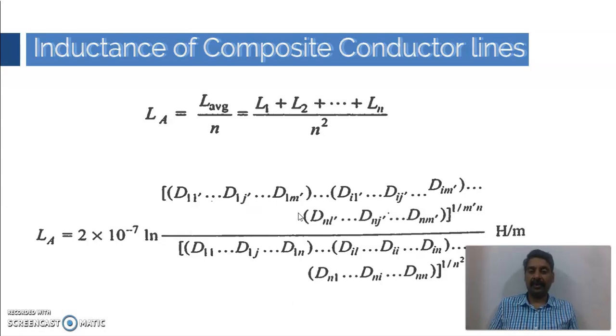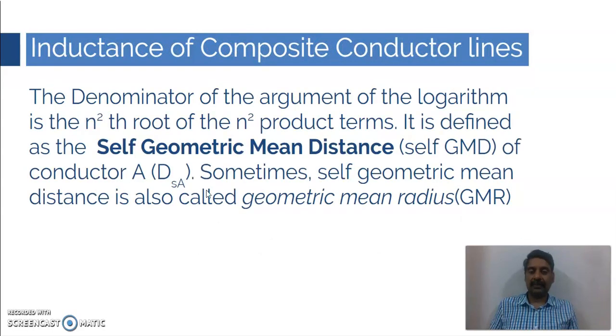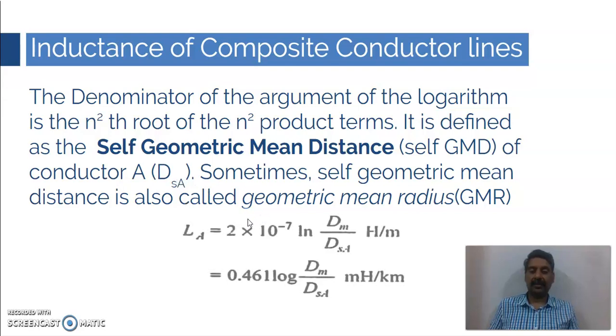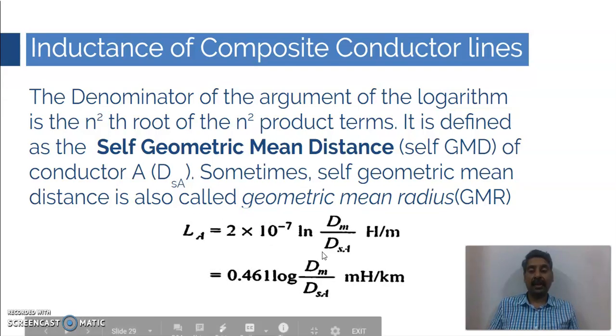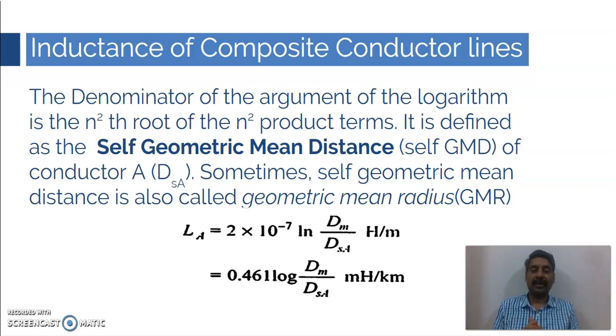If you replace all these terms with their equivalents — DSA in the denominator and DMA in the numerator — the equation reduces to a simple form, similar to what we derived for the single-conductor case. LA = 2 × 10⁻⁷ × ln(dm / DSA) Henry per meter, or equivalently 0.4611 × log(dm / DSA) millihenry per kilometer. This is how you calculate the inductance of composite conductor lines.